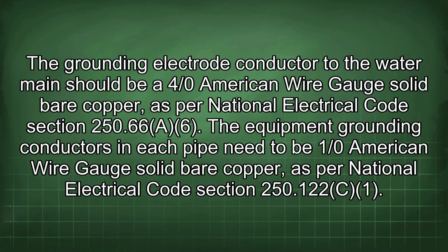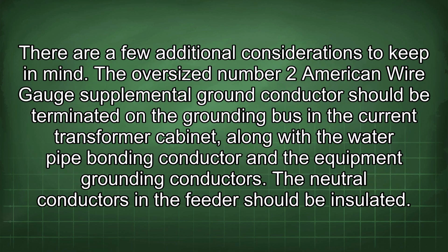The grounding electrode conductor to the water main should be a 4/0 American wire gauge solid bare copper, as per National Electrical Code Section 250.66(A)(6). The equipment grounding conductors in each pipe need to be 1/0 American wire gauge solid bare copper, as per National Electrical Code Section 250.122. There are a few additional considerations to keep in mind.